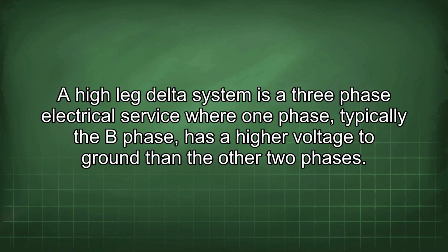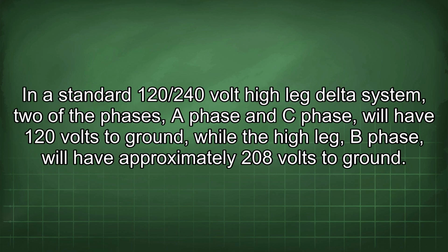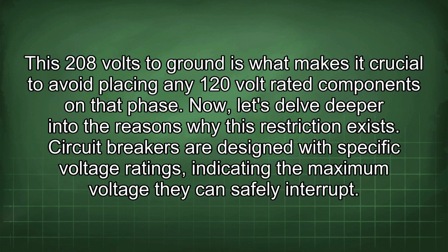A high-leg delta system is a three-phase electrical service where one phase, typically the B phase, has a higher voltage to ground than the other two phases. In a standard 120/240 volt high-leg delta system, two of the phases, A phase and C phase, will have 120 volts to ground, while the high-leg B phase will have approximately 208 volts to ground. This 208 volts to ground is what makes it crucial to avoid placing any 120 volt rated components on that phase. Now let's delve deeper into the reasons why this restriction exists.